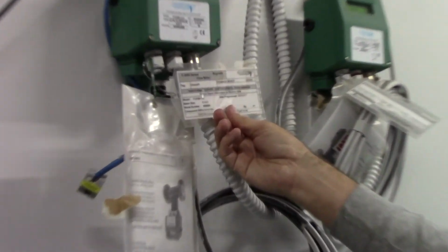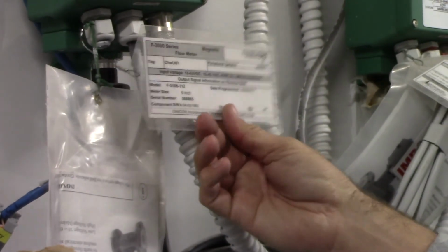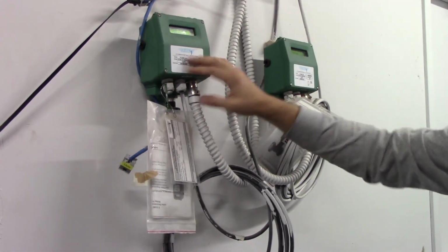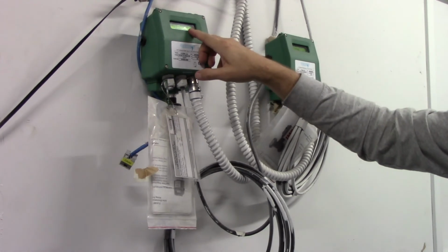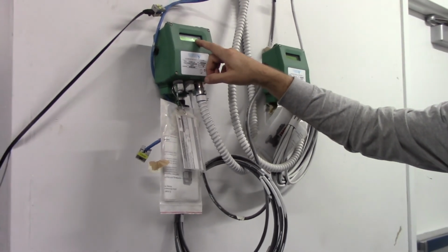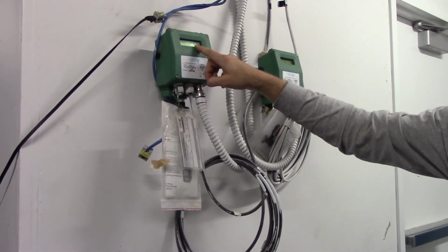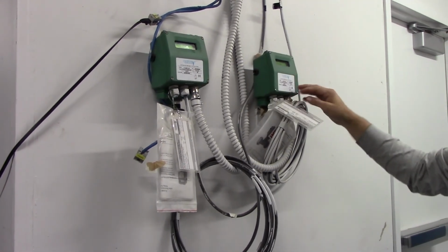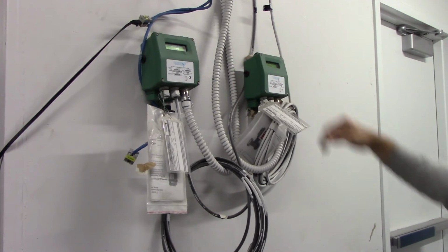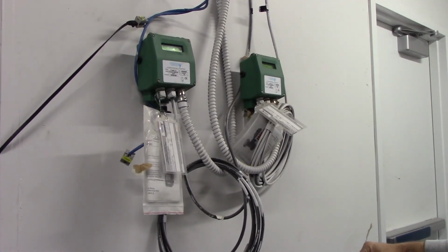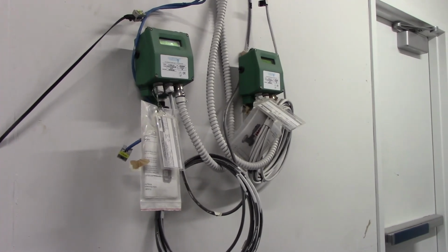This is chilled water utility flow, which is the 56-degree water chilled loop. Same kind of display. We're showing 217 GPM going out to that loop right now. And to the right of that, you have your hot water loop. We're showing 95 GPM on it. So these 2 things go to your chill beams.